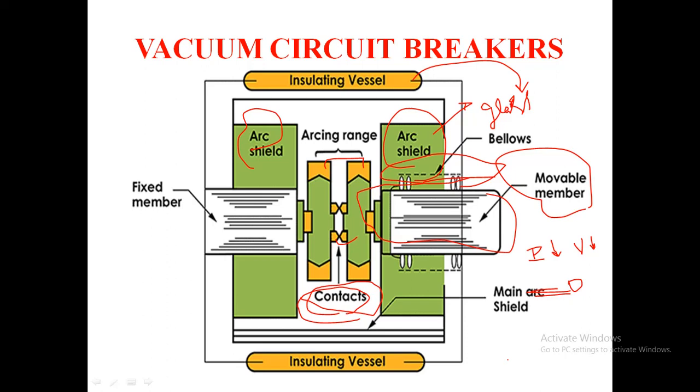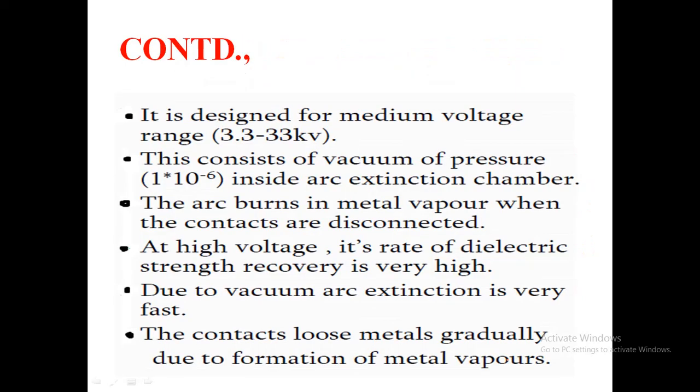So after final arc interruption, the dielectric strength, which is peculiar in the vacuum circuit breaker. This is mainly suitable for capacitor switching, and small currents are interrupted before the natural current zero. Coming to the chopping levels, as the vapor pressure of the cathode material increases, the chopping level will be lower. And the thermal conductivity: if thermal conductivity is low, the chopping will also be low.